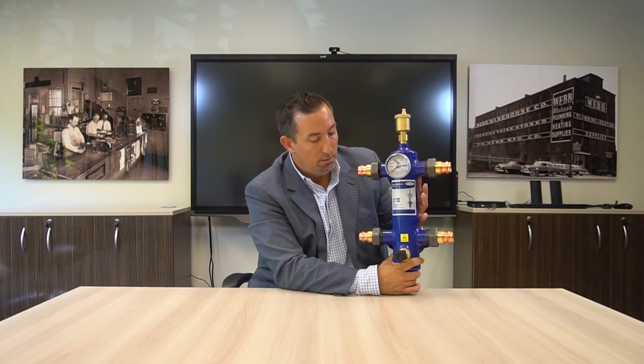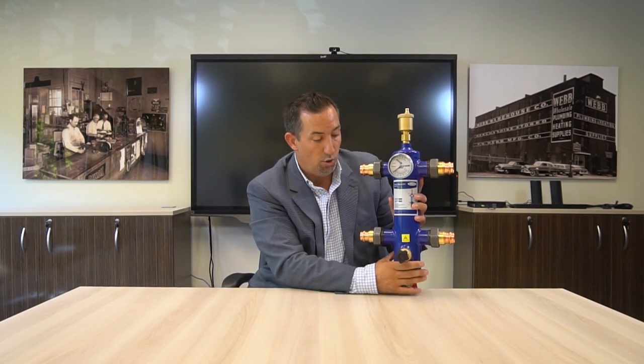Why is it important to get rid of air in a system? Air is the number one catalyst for corrosion. If you have corrosion in the system, that's going to lead to breaking down of the heat exchanger, pinholes, premature leaks. Also, we all know that air does not transfer heat as well as water. So when you get airbound zones in a system, you're reducing your efficiency on the boiler or combi, and you could be creating rooms that just don't heat up as fast or at all.